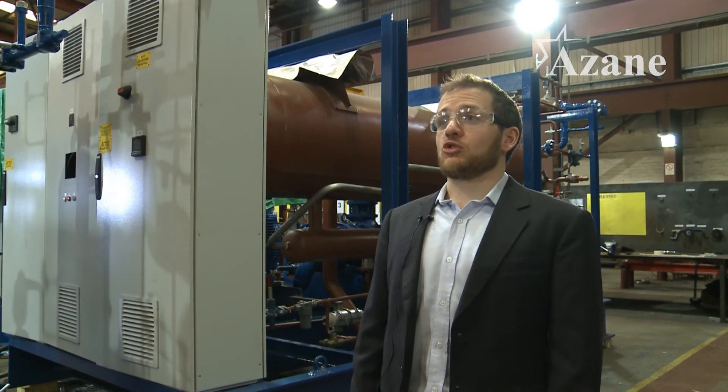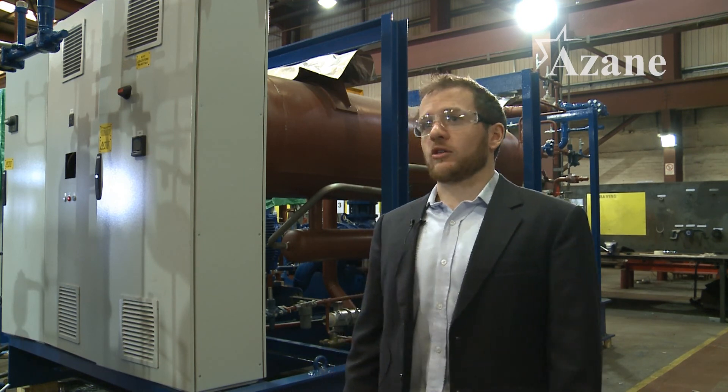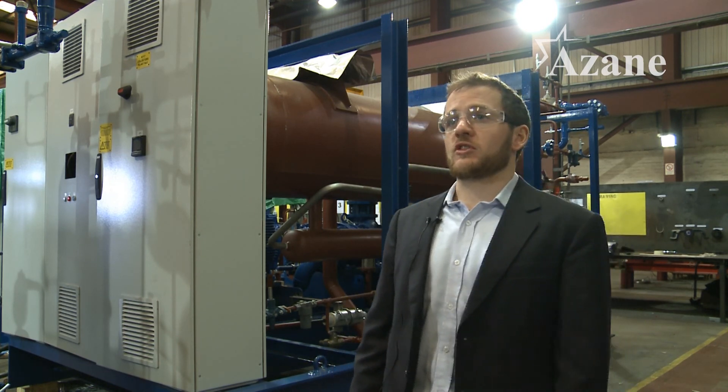The Azane Freezer uses a unique reverse cycle defrost system. This effectively turns the air cooled condensing unit into an air source heat pump, leading to a very fast and efficient defrost. It also reduces the complexity of the system because we don't require the hot gas valve station that would be required for a typical hot gas defrost system.